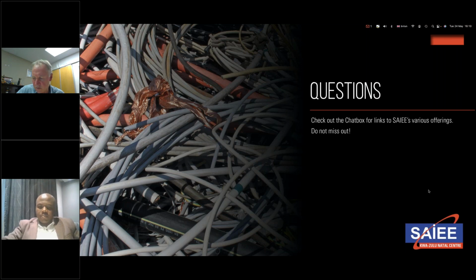The issue with these kinds of cables that one would use aluminium or potentially CCA in would be fixed installation cables, and for those cables the defining criteria would be the insulation, that as you bend the cable you don't want the insulation to be damaged from the pressure exerted by the layers above, whether it's copper tapes or copper wire screening or armoring that exerts pressure on the bottom layers.